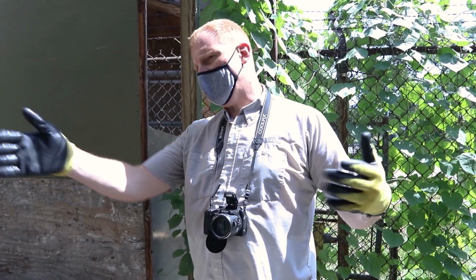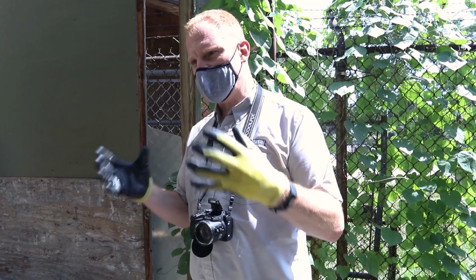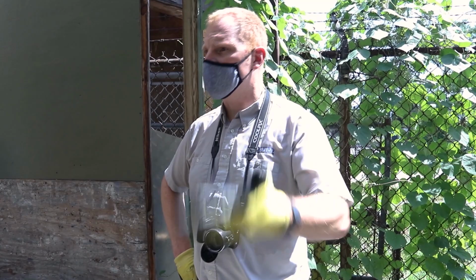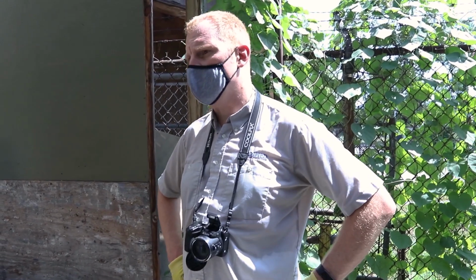We have plumbing run to what is effectively an exterior part of the building. They put some insulation up there. They put a little space heater in there to try to protect it. So you're just going to have to be very careful about making sure that that heater keeps the temperature in there above about 7 degrees Celsius, or you will burst the plumbing in the wintertime.